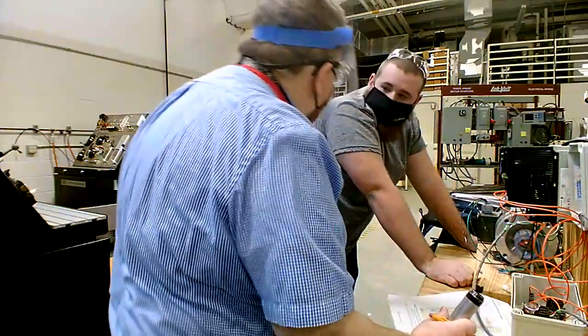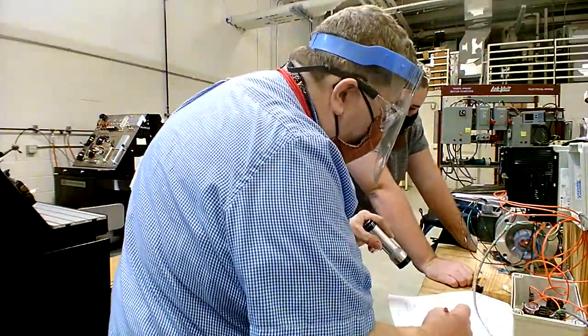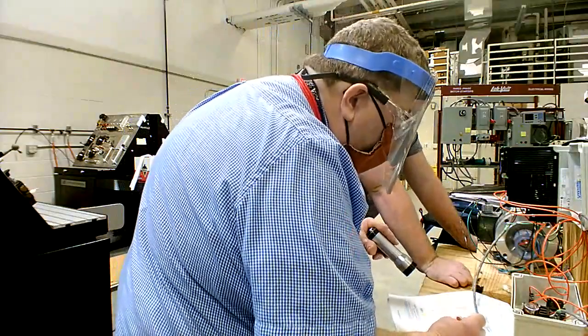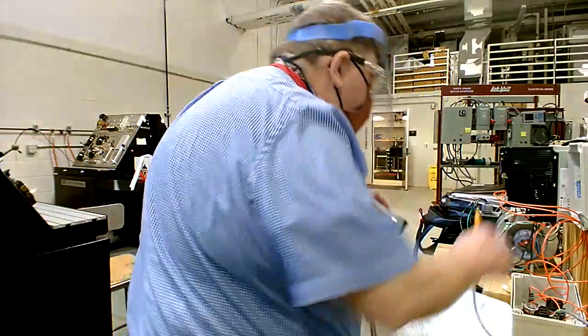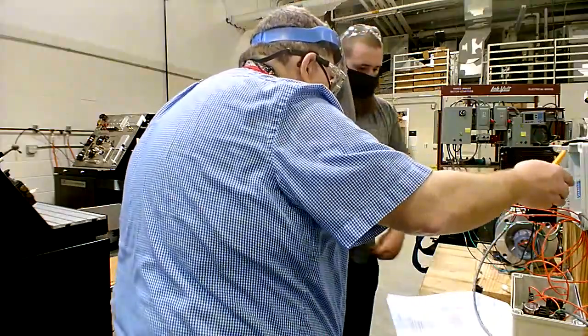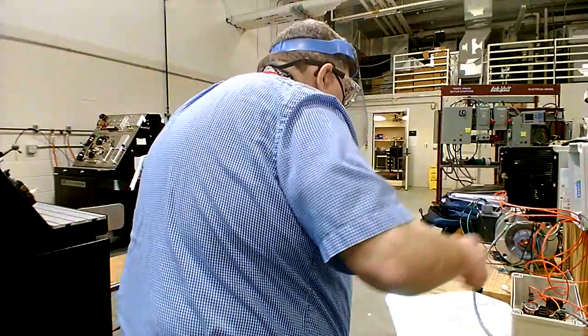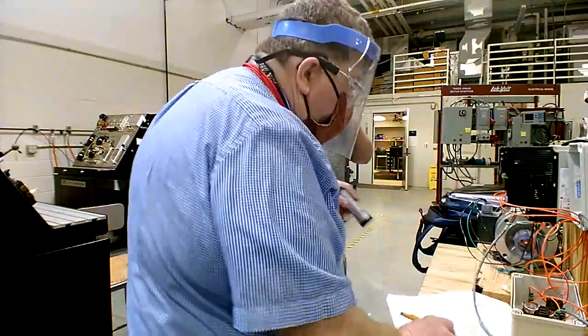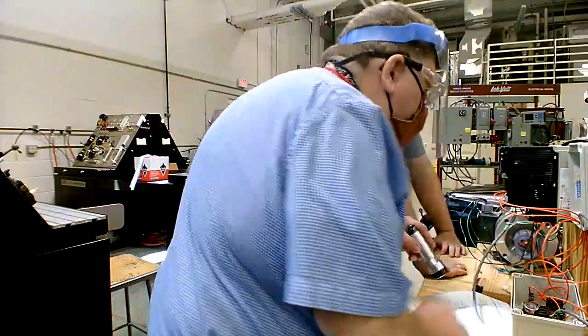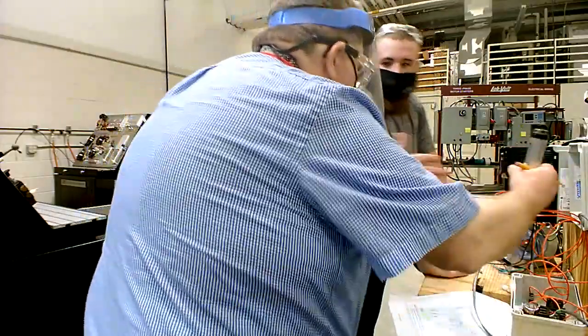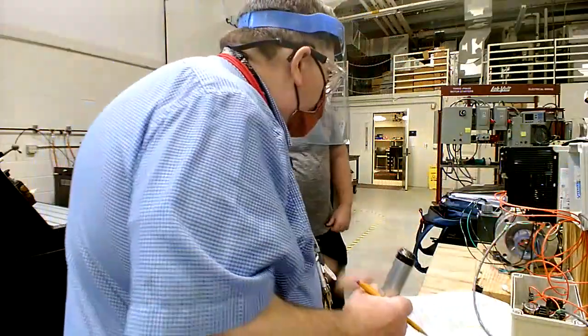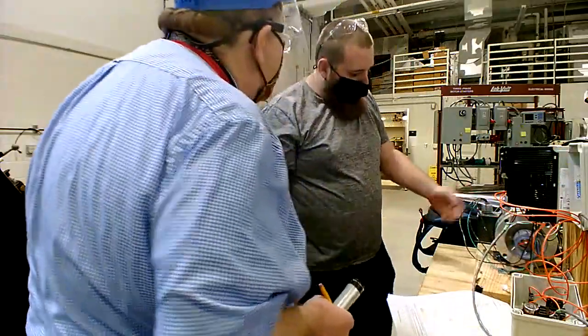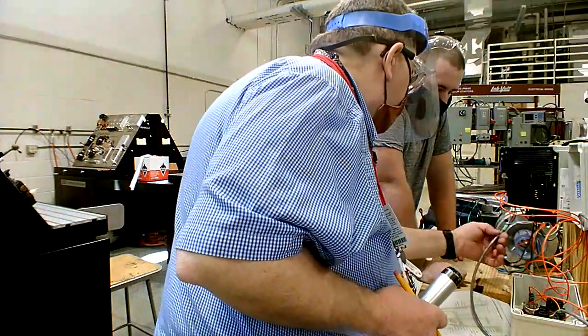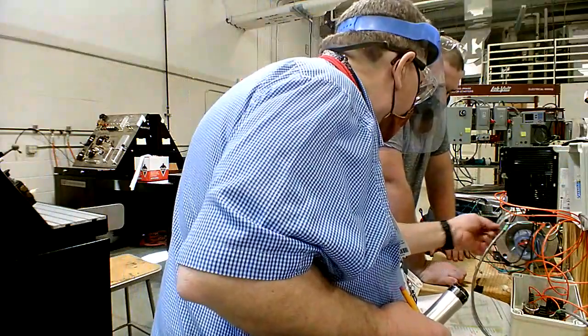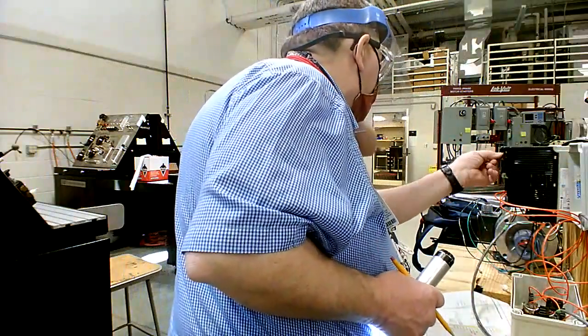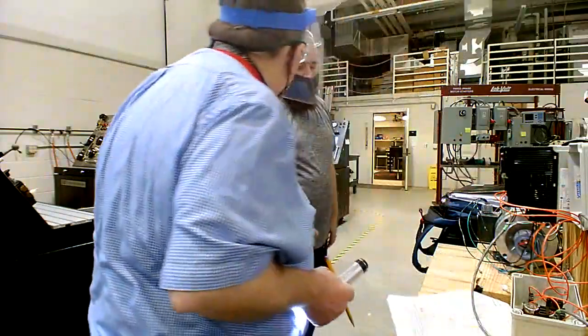Now, on the other one, on the PowerFlex 4, they've actually got a terminal 4 ground. And it still boggles my mind that they don't have a shielded cable there. If you're close range like this, you're okay. But on longer range, you've got to have shielded. If you put the cables beside other wiring and you don't shield it, then that interference can get in there and confuse the drive. It can make it think you're rocking the speed like this. It can be erratic on the speed.